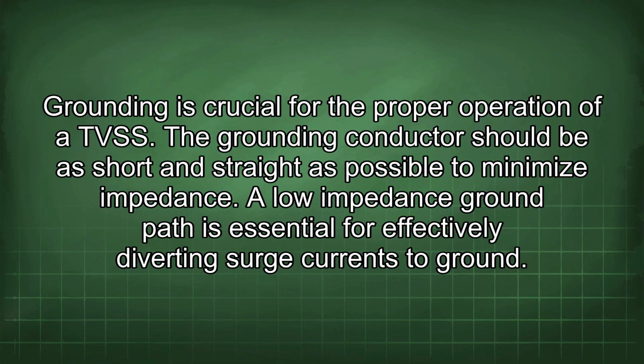Grounding is crucial for the proper operation of a TVSS. The grounding conductor should be as short and straight as possible to minimize impedance. A low impedance ground path is essential for effectively diverting surge currents to ground.